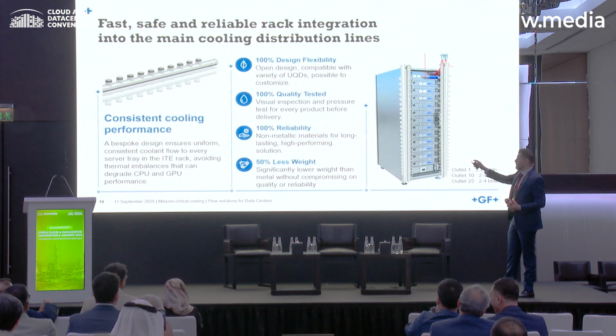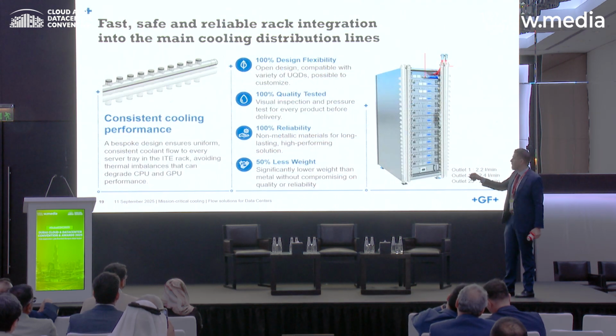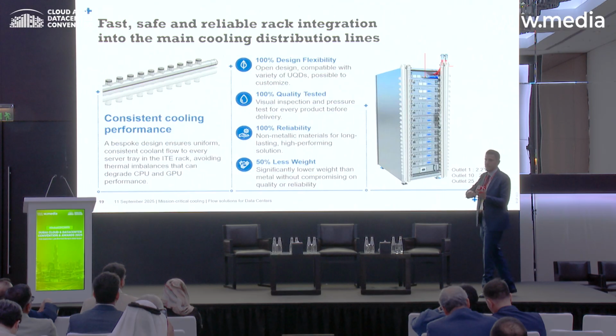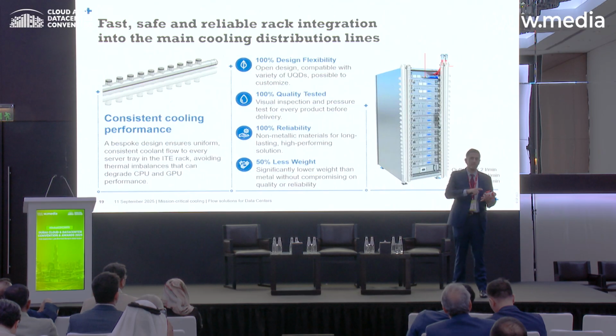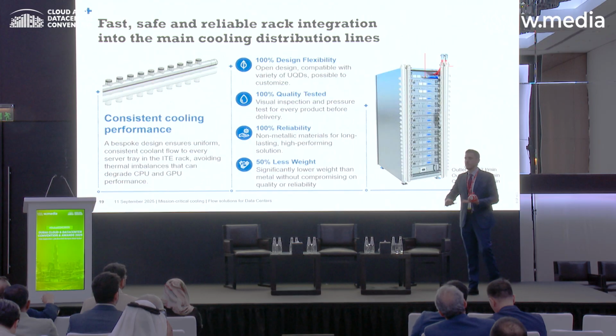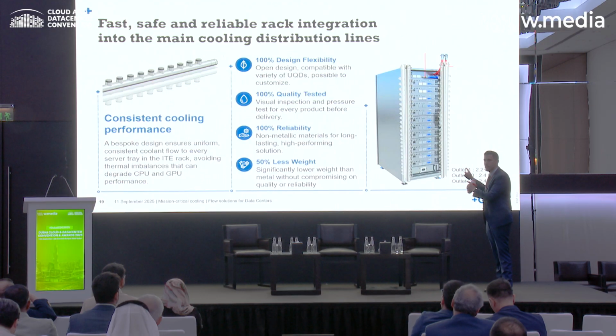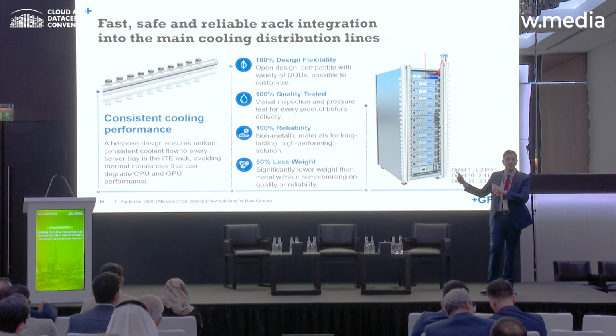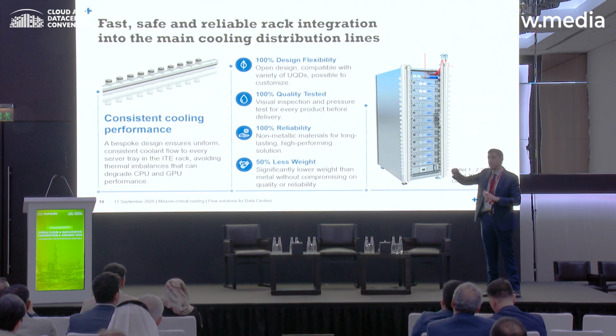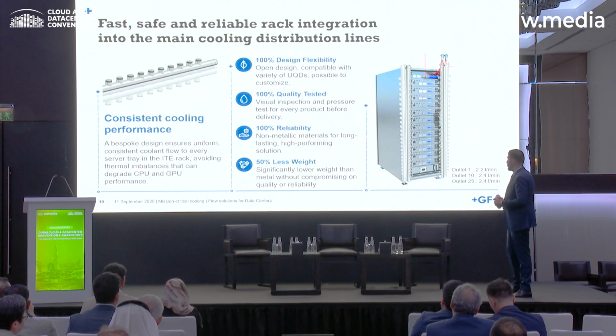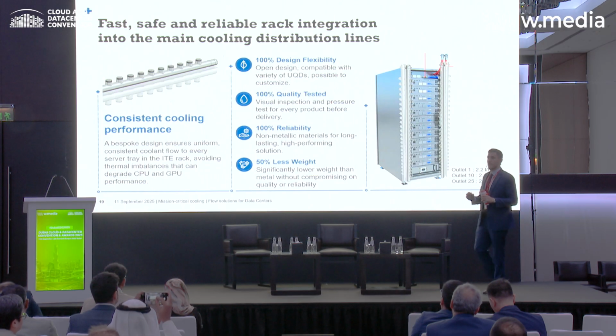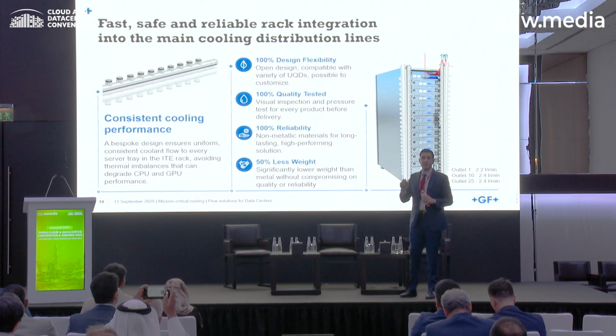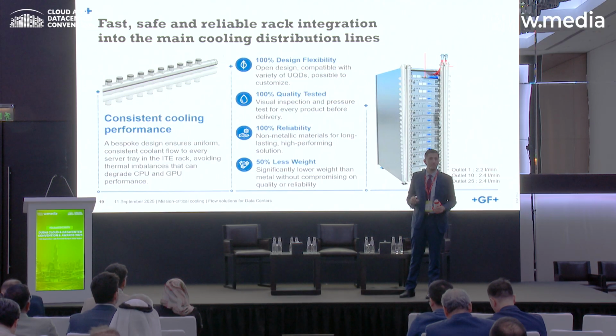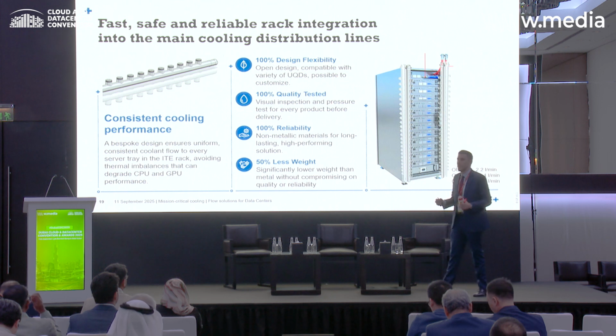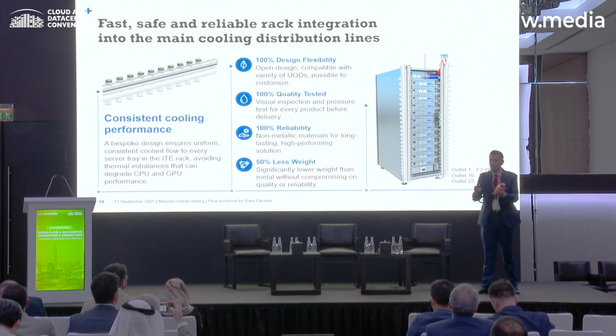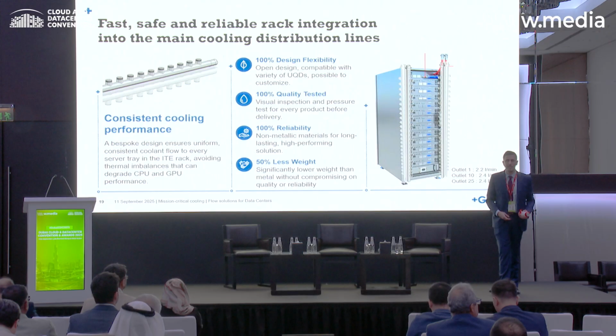The material selected for this is PVDF, with advantages not only in weight reduction, at least 50%, and corrosion resistance, but also serving a very important feature: consistent cooling at all server levels. With a stainless steel quadratic shape, the flow rate at each outlet and port is not maintained, is not consistent, so the cooling is not consistent. This is simply because of the geometry forced by the material.